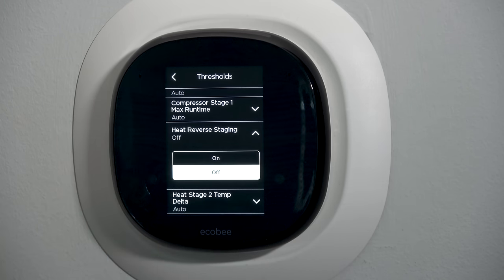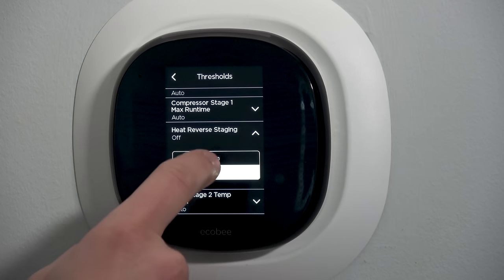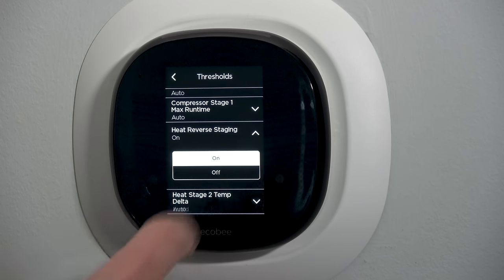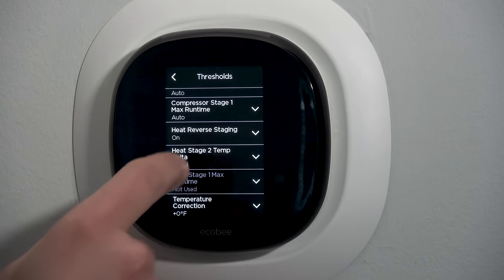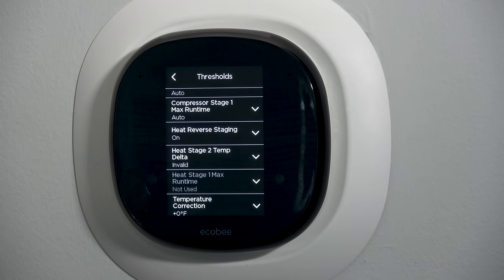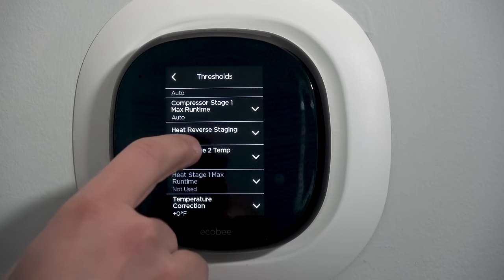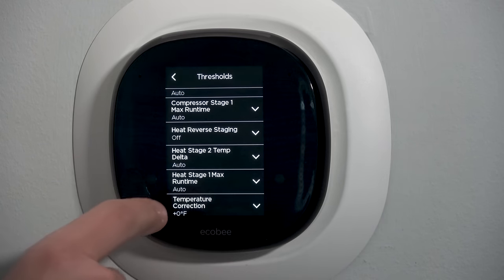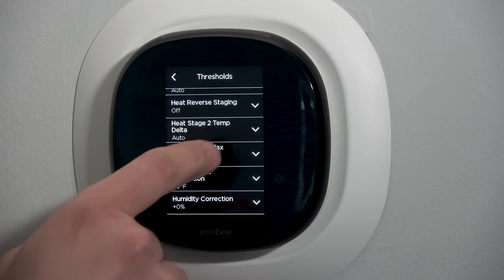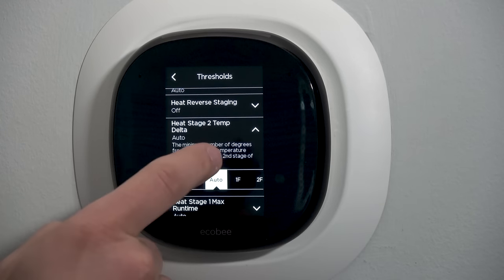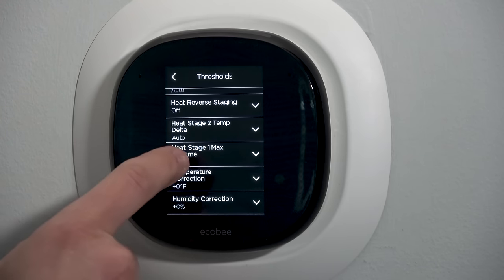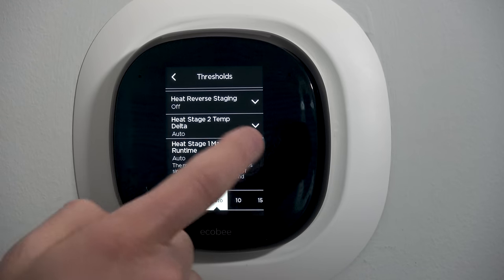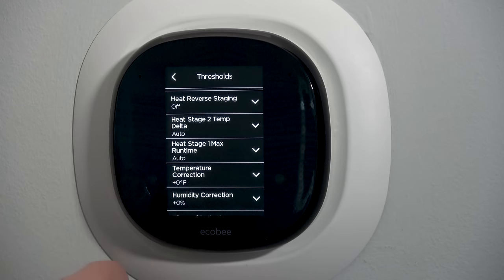Heat reverse staging works just like the cooling one — I would turn that on. If you turn it on, the stage two temperature delta is automatically handled by reverse staging. If you leave it off, you have access to stage two temperature delta and heat stage one maximum on time, which work the same as the cooling equivalents.